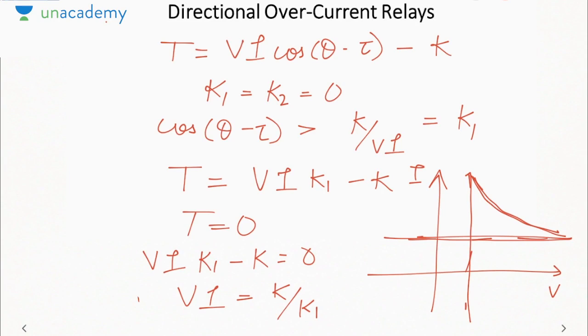Similarly, the potential transformer will step down the fault voltage for relay operation. Then, based on the angle, or based on the fluxes produced by these two quantities, the directional overcurrent relay will operate. For maximum torque, the angle between these two fluxes must be 90° so that maximum torque can be produced. The characteristics of this relay on a VI plane look like a hyperbola, which has certain minimum limits because it has an overcurrent unit as well.